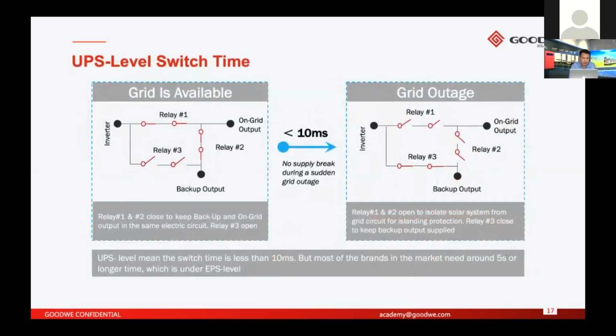This is another feature. We call it the UPS level switch time. It means that switching from on-grid mode to off-grid mode takes less than 10 milliseconds. It's a UPS level, an uninterrupted power supply level. Here is a brief introduction. In on-grid mode, this is the inverter side, this is the on-grid side, and this is the backup supply. There are two relays here, and they are closed. So if the grid is normal, the backup supply and on-grid supply are connected in the same electrical circuit.